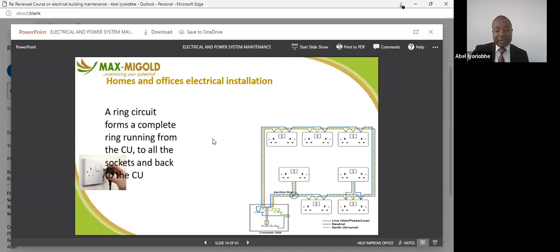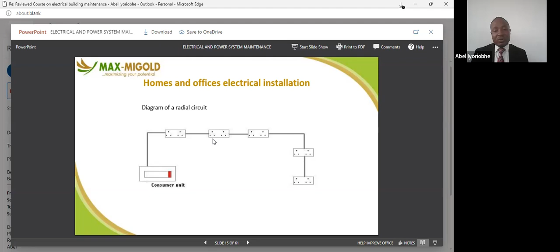So we have another type, the radial, which is used in modern day installation, where a cable runs from the distribution board to where the socket is, or where the electric cooker is, or the laundry room, instead of doing a ring form of installation. You may spend more at the initial stage, but in the long run you are saving costs and preventing damage to the installation.